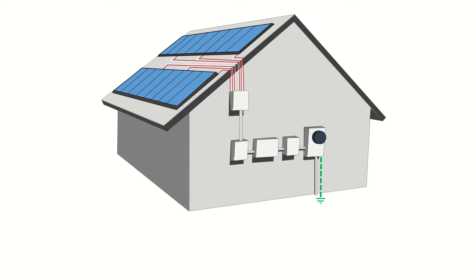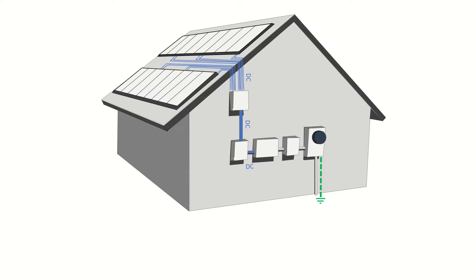For instance, if you wanted to turn off power to the inverter, then you could throw this AC disconnect, and this will create a safer environment for anyone that might be working on the equipment downstream, avoiding any possible encounter with live voltage. DC disconnects are switches that complete or interrupt the flow of DC electricity or direct current.